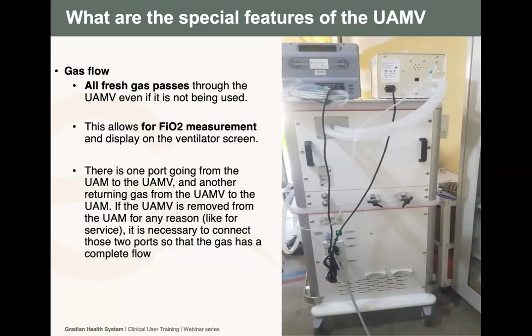Thank you, Ken and Daba. So you can disconnect the two tubes and loop them from behind, and then you do manual ventilation. Hope I've answered your question. Okay, so it's basically these two limbs, these two tubes that we are seeing, and then you connect them together, and then you do manual ventilation, yeah? Exactly. So you just disconnect the two tubes, and then you get one tube. You loop it from the two ports that come from the machine, the one coming from the vaporizer and the one going to the breathing block. So it's more like a loop. Ah, okay.